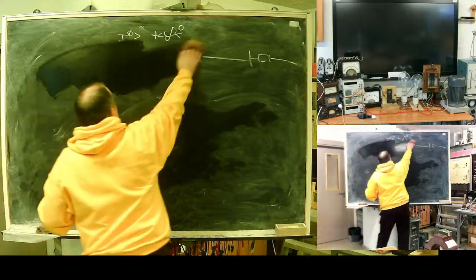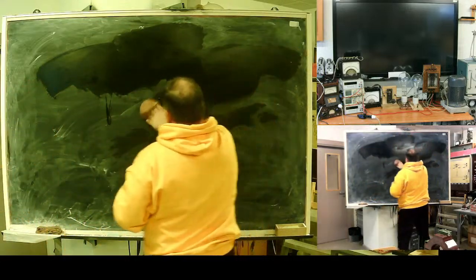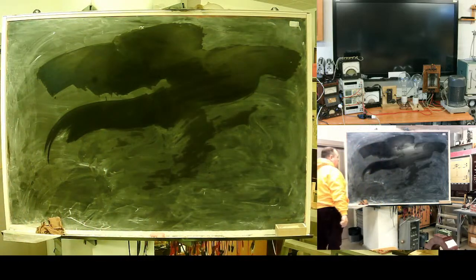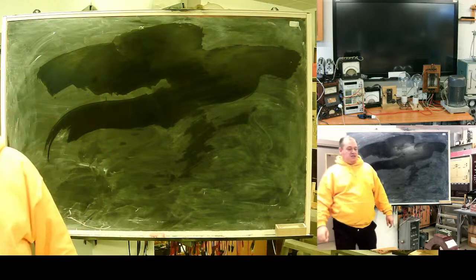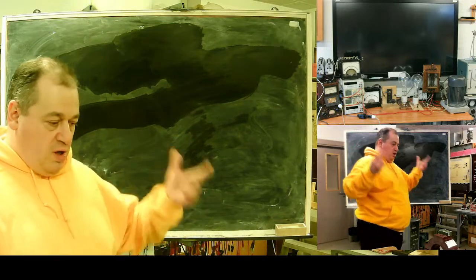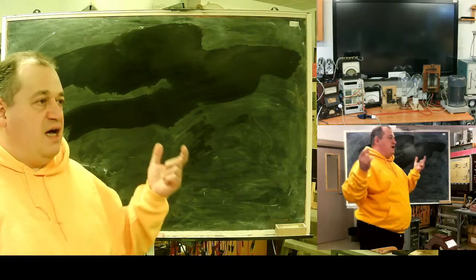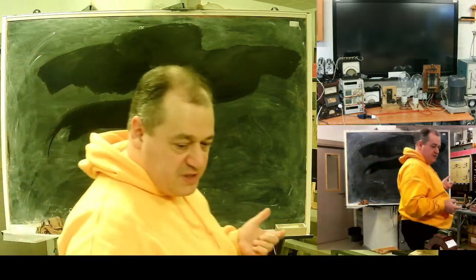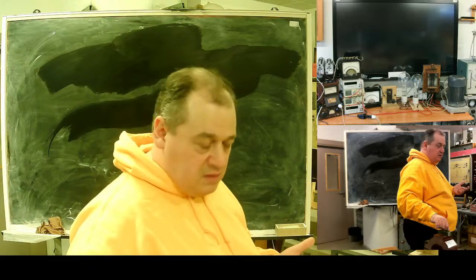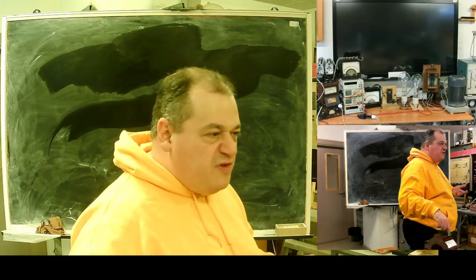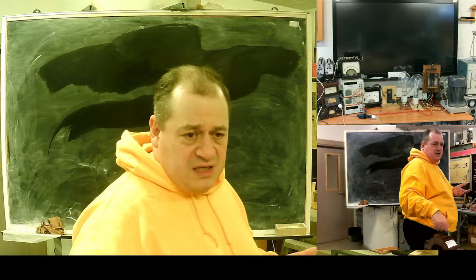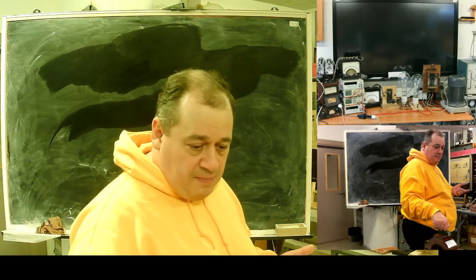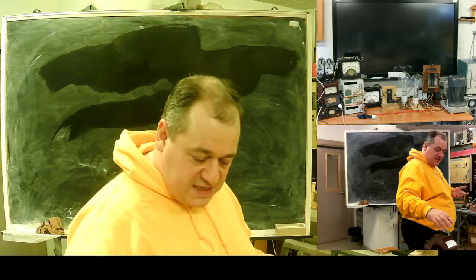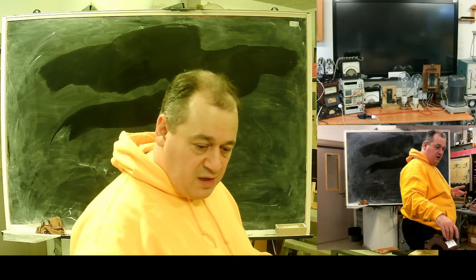But where is the tricky moment? Earth fault currents are small. Imagine, you have a network with 600, 1000, 2000 amps of normal current. Earth fault, 15 amps, okay, 20 amps. Nothing in comparison. You need to have quite a sensitive relay. Yeah?